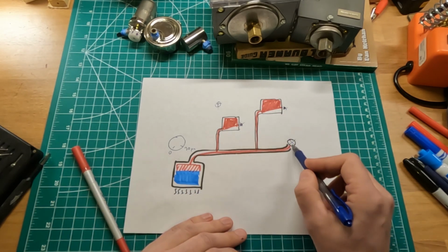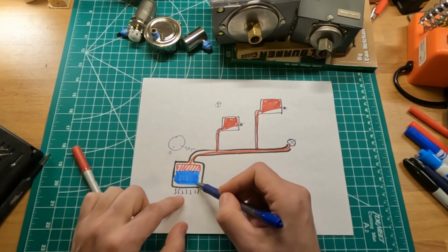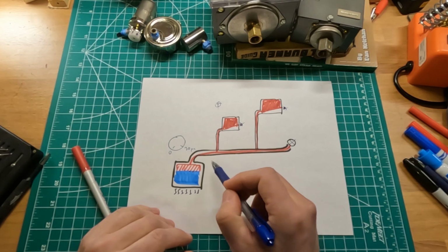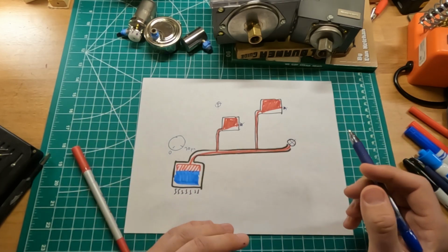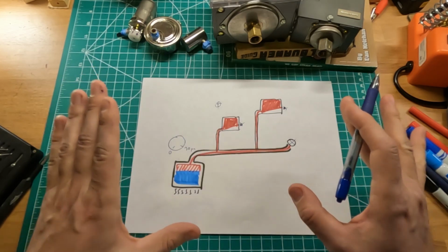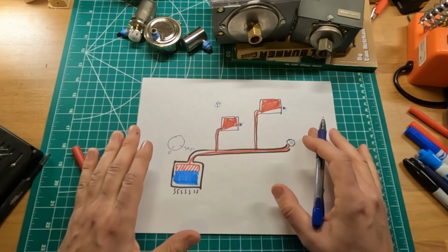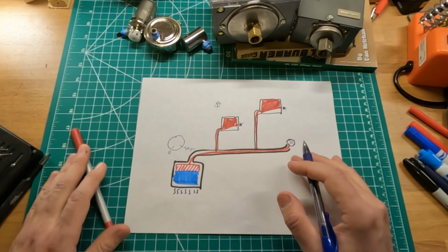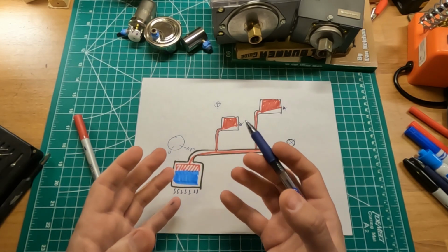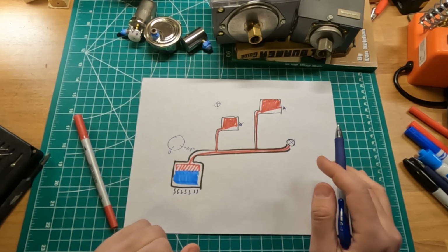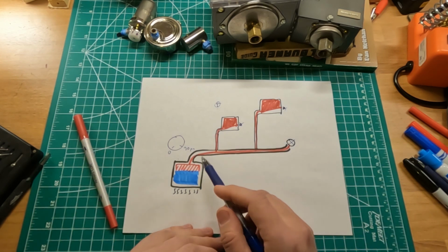So when those vents open up, then if the thermostat is still not satisfied, the boiler kicks in and starts producing more steam, and that steam once again gets redirected to all sorts of places inside your system. The bottom line is that you do not want pressure buildup in your system. You want to work with as low pressure as possible, because any rise in pressure means you're raising pressure in the boiler, which means the steam has nowhere to go, and that means your boiler keeps on producing more steam, and you're wasting that energy because that steam really has nowhere to go.